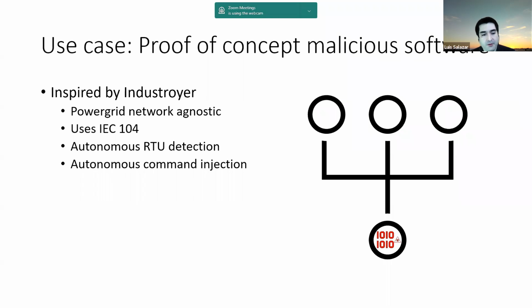After we developed this framework, we needed to test it somehow. So, inspired by Industroyer, we came up with a proof-of-concept malicious software that uses IEC 104 the same way Industroyer did. Like the latest known Industroyer, it is completely autonomous. It detects the RTUs and makes a command injection that could potentially generate a blackout in the power grid system.